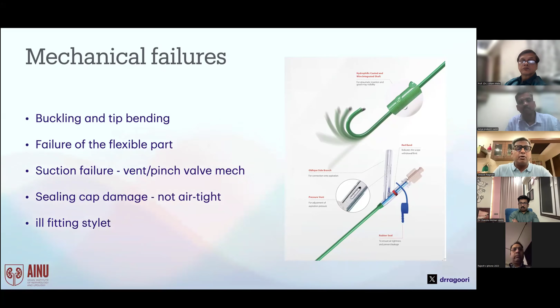An ill-fitting stylet cannot allow the access sheath to go in completely. When you come to the negative pressure complications, mucosal tenting into the access sheath can happen, where you suck in and the mucosa comes into the access sheath. If you realize it very early and let go of the suction, there's not much damage done. But if it is constantly happening, you will cause some trauma. It is a localized mucosal trauma, or it can occur by using a damaged atraumatic tip in the suction ureteric access sheath.